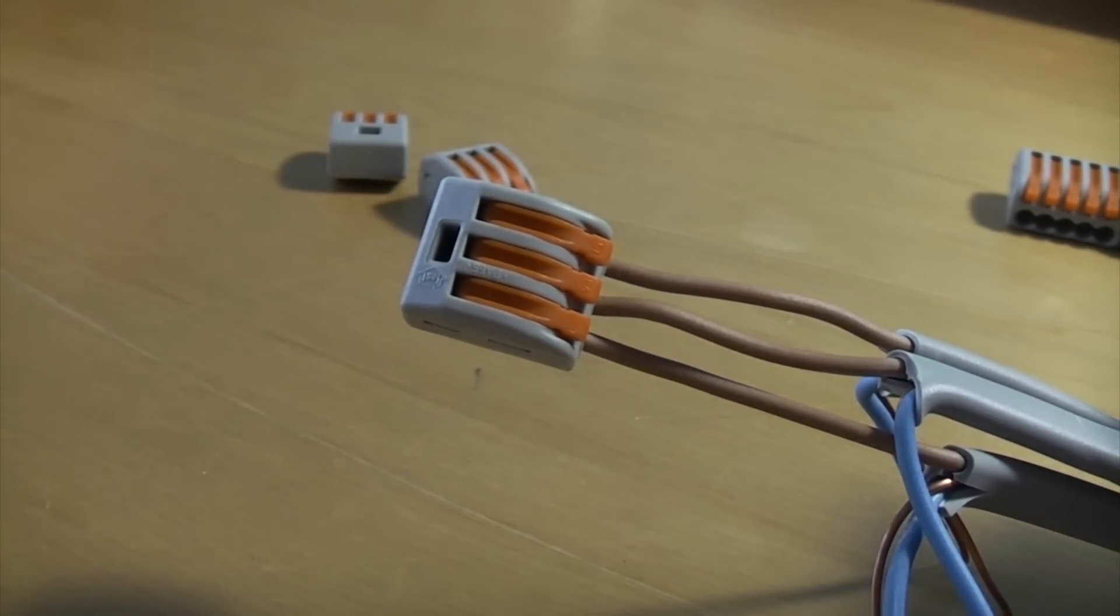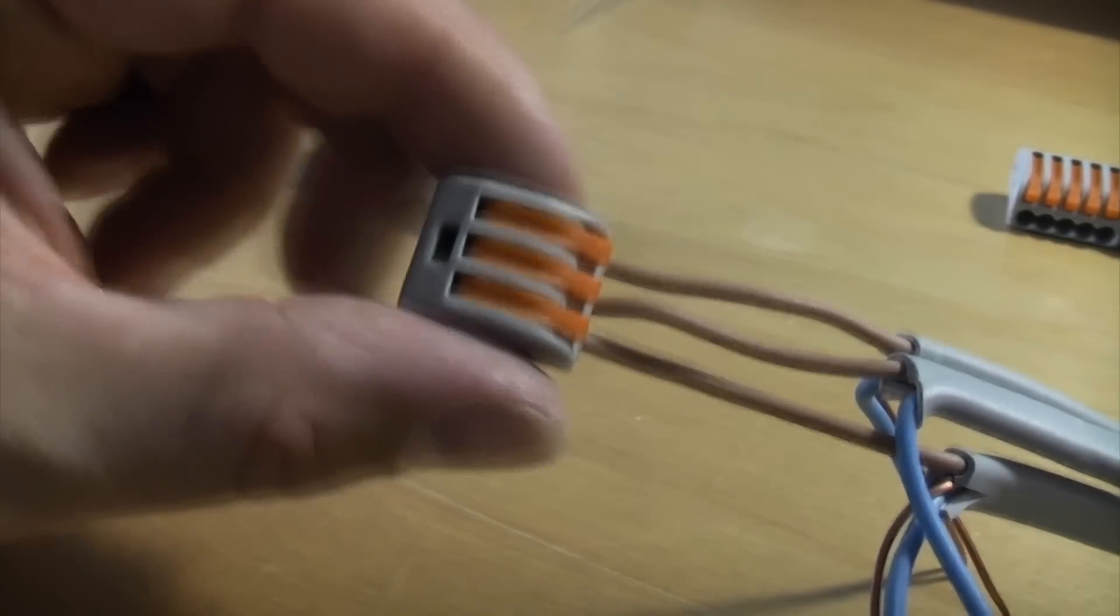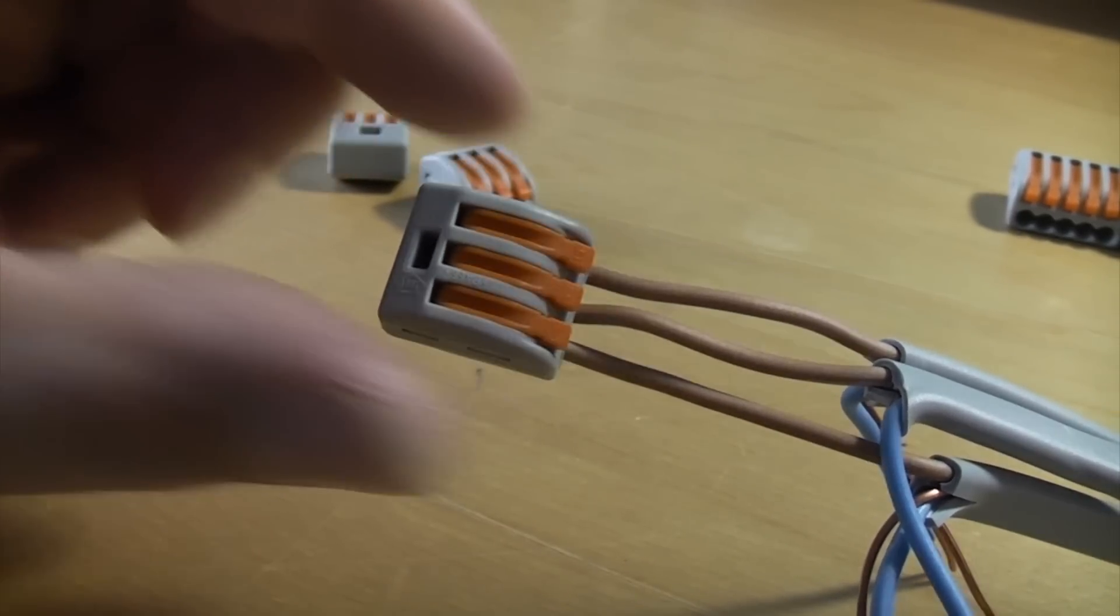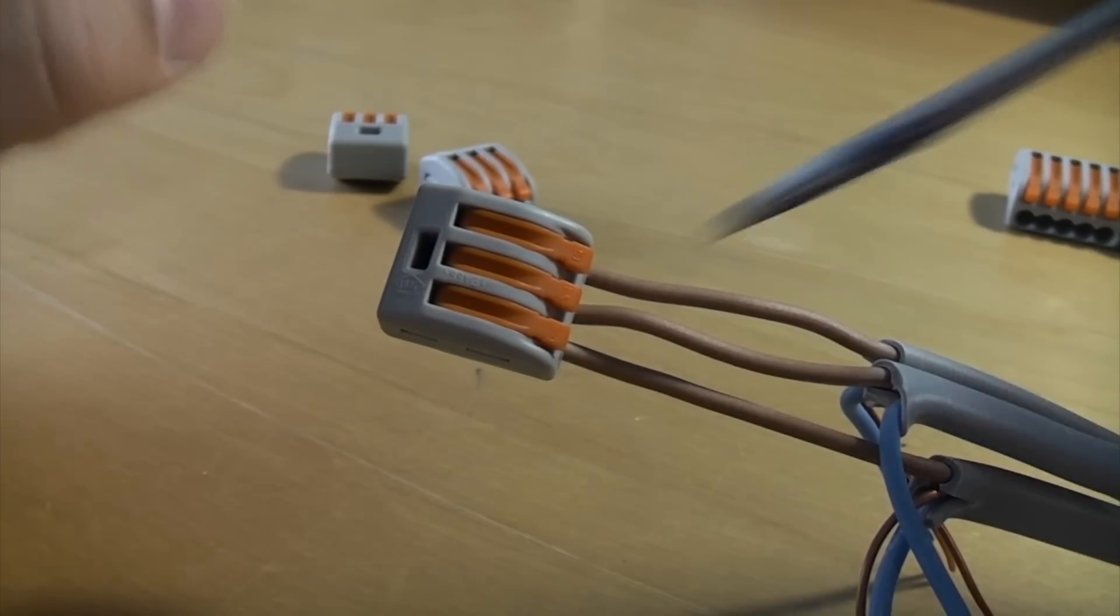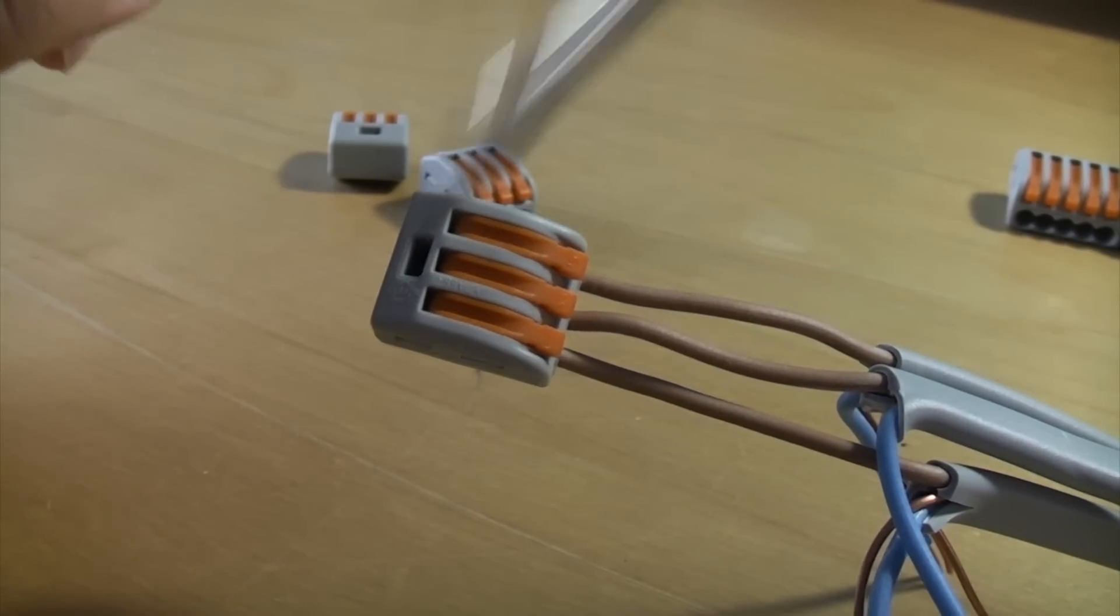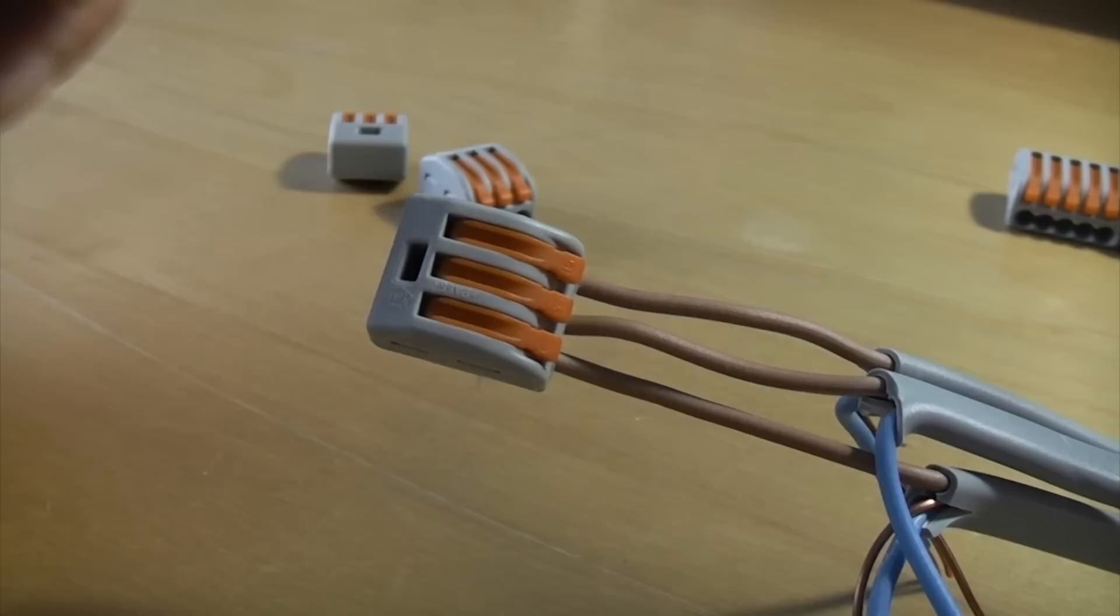Another good thing about these is they actually have a tiny hole there where you can actually put a probe in. So if you ever needed to do any testing, you don't need to undo any of the clamps. All you need to do is push your probe into the dedicated terminal there and you can test it and make sure that it is live.